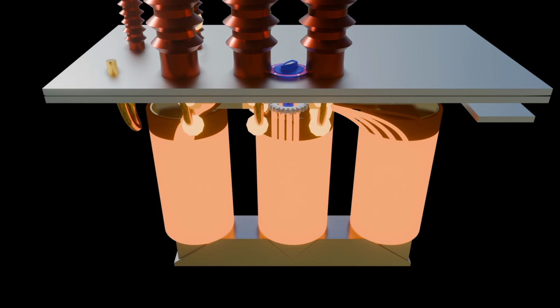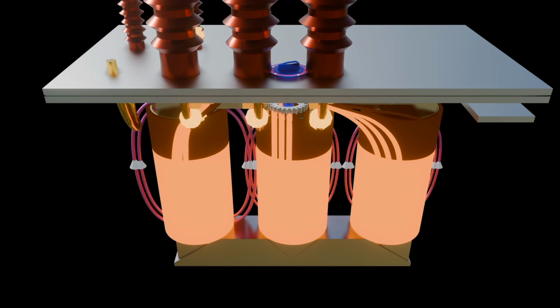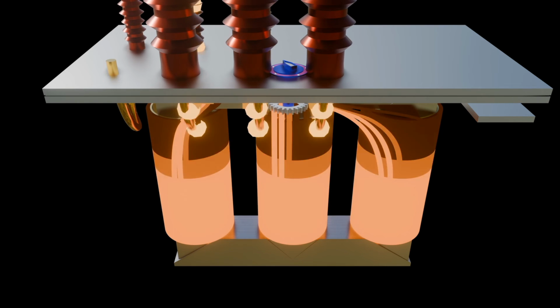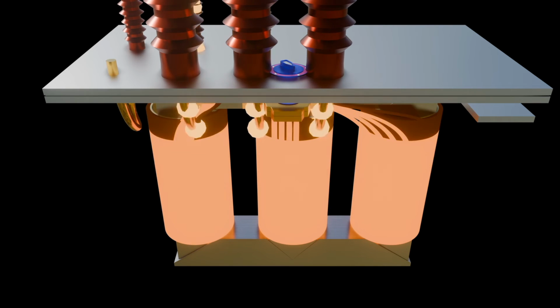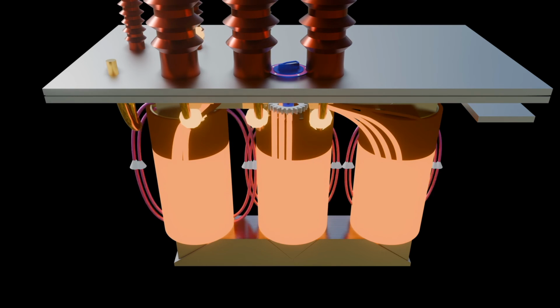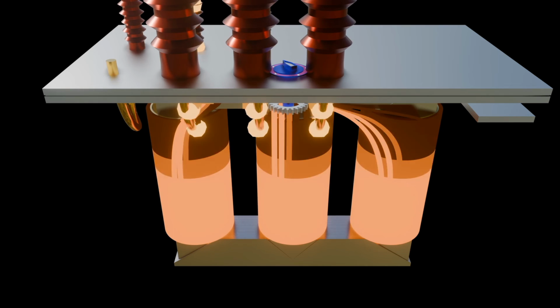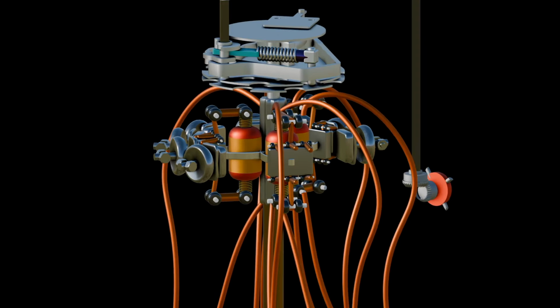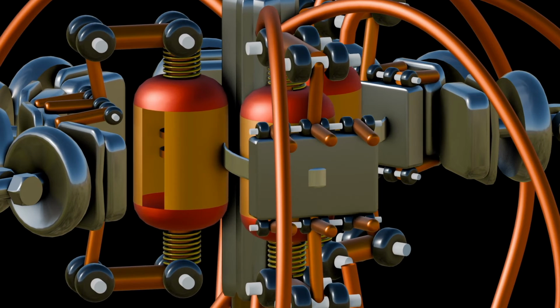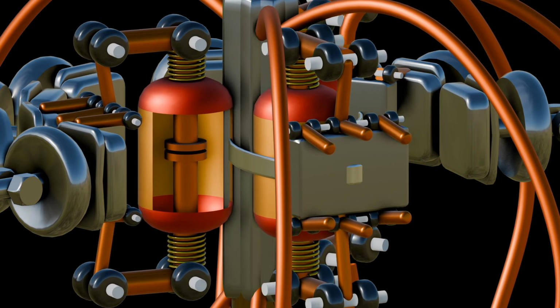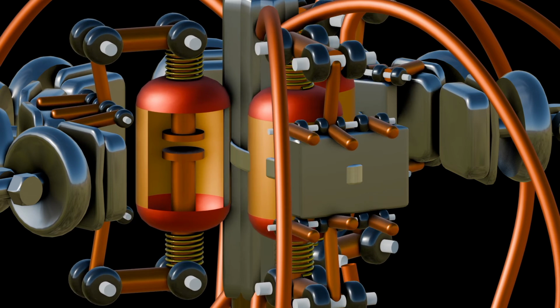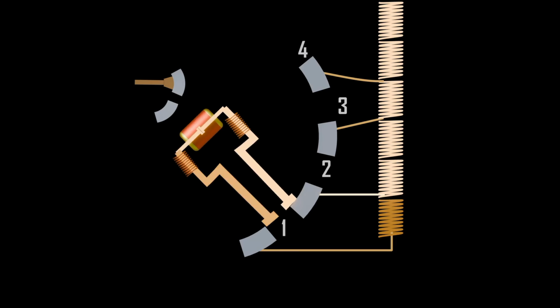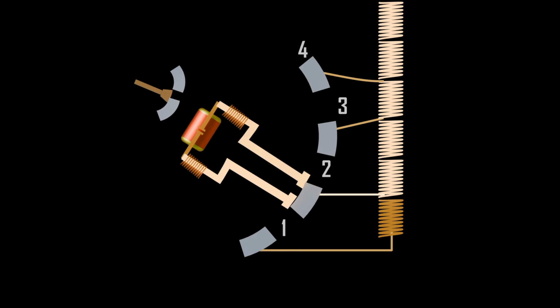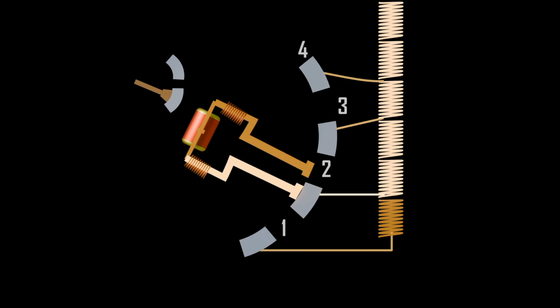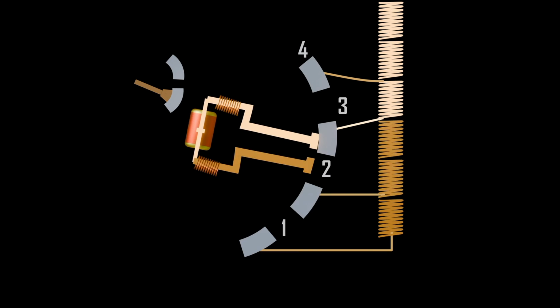But remember, we were changing these taps when the transformer was off and manually. We can't do this tap changing when the transformer is on load. And thus is where on-load tap changers come in. It has many components such as vacuum switches, bypass switches, selector switches, sensors and many more. It has to follow a certain procedure for the safety of the transformer, thus it uses remote control and has a control panel. Check our next video for more about OLTC.